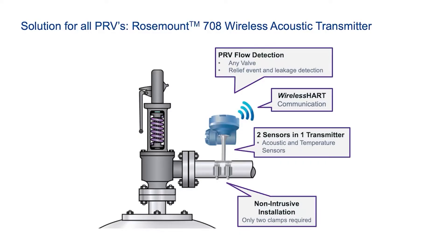The Rosemount acoustic transmitter is affixed to the PRV's outlet piping and measures sound levels in the pipe that occur with a valve opening or closing as well as any temperature change due to flow during an overpressure event.